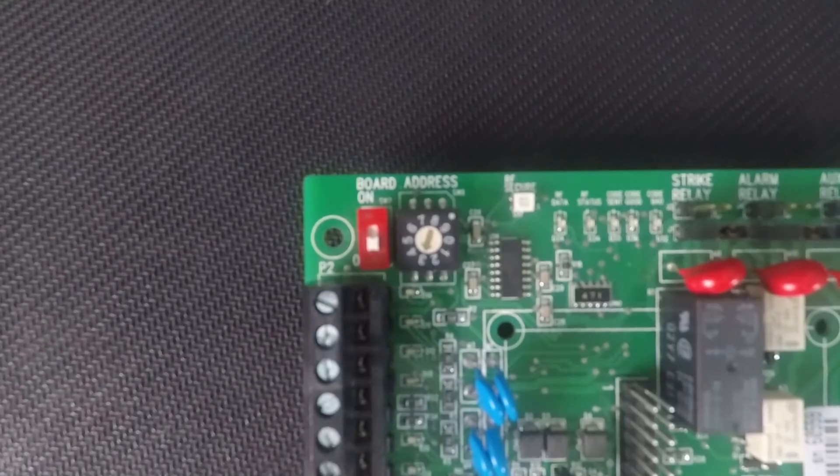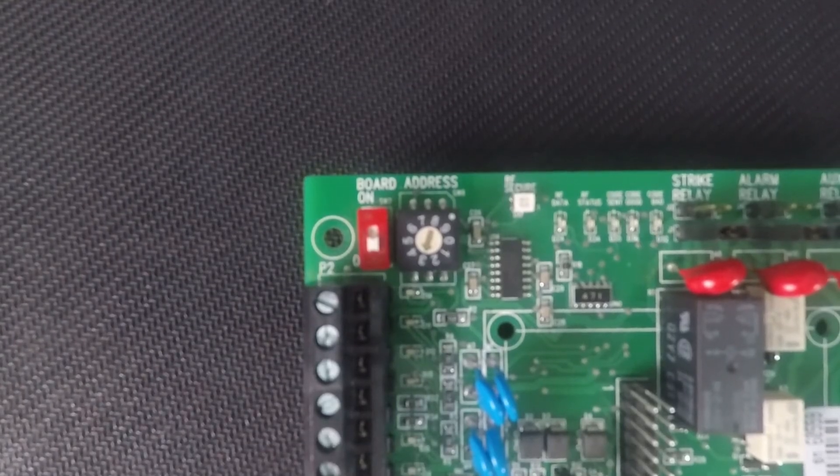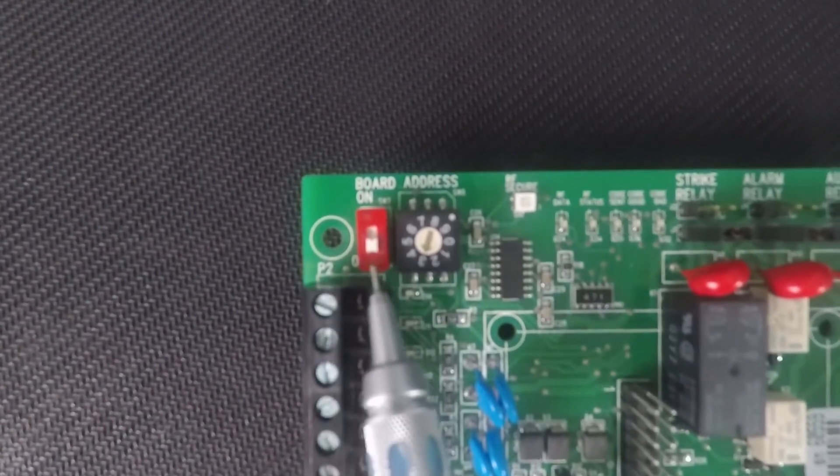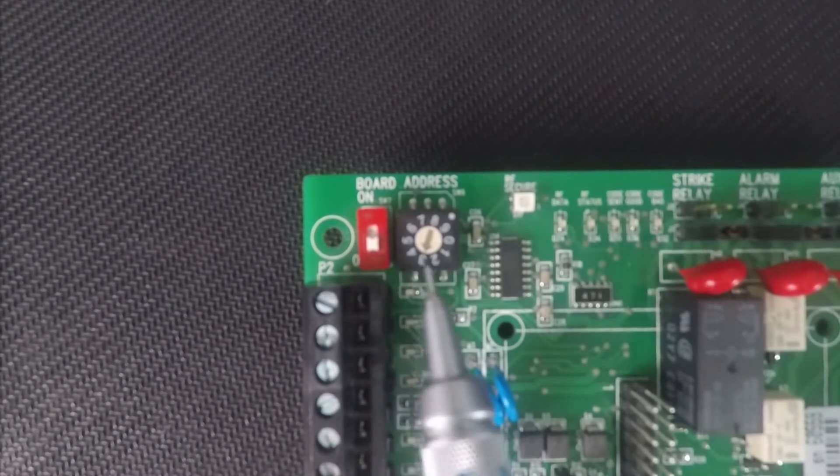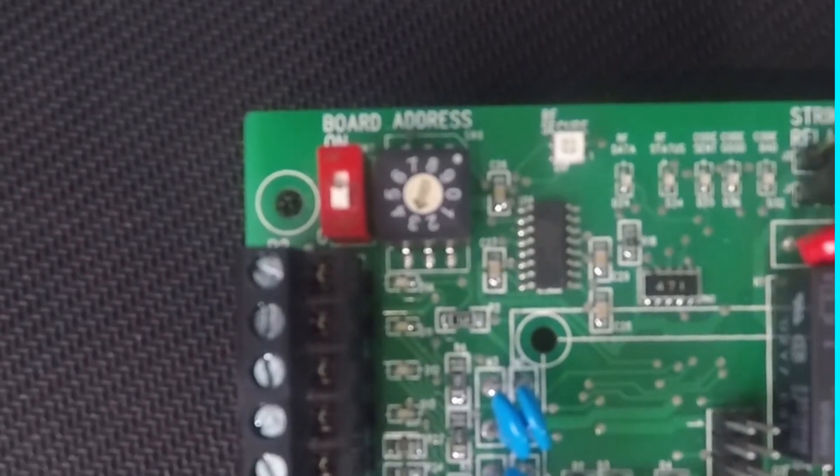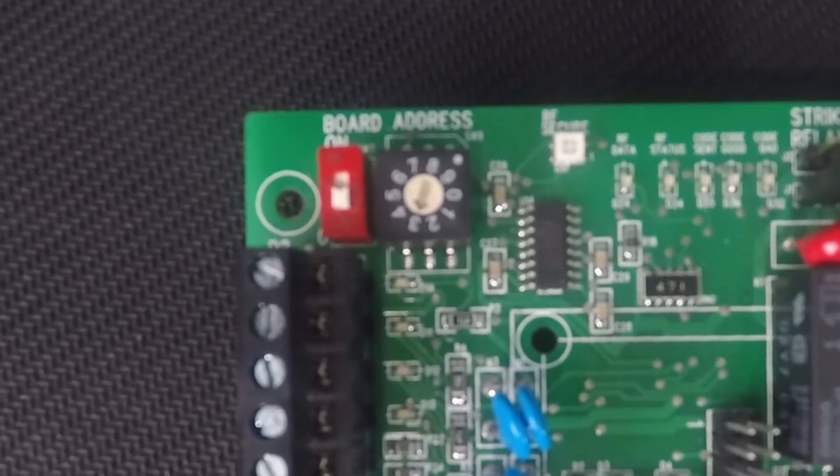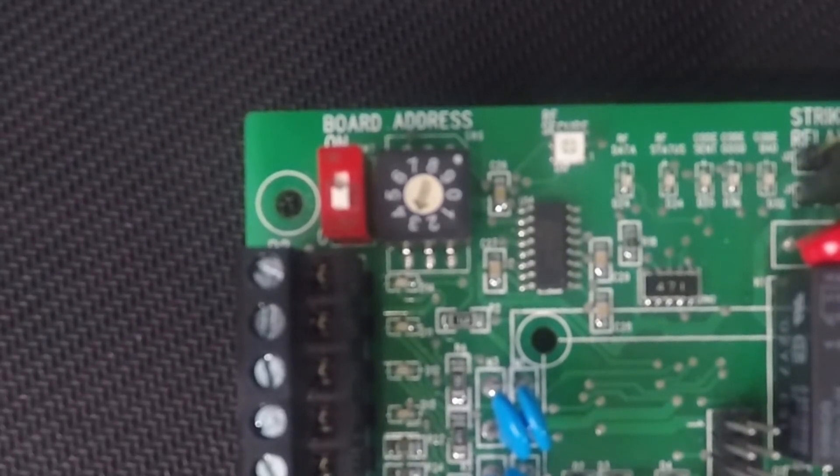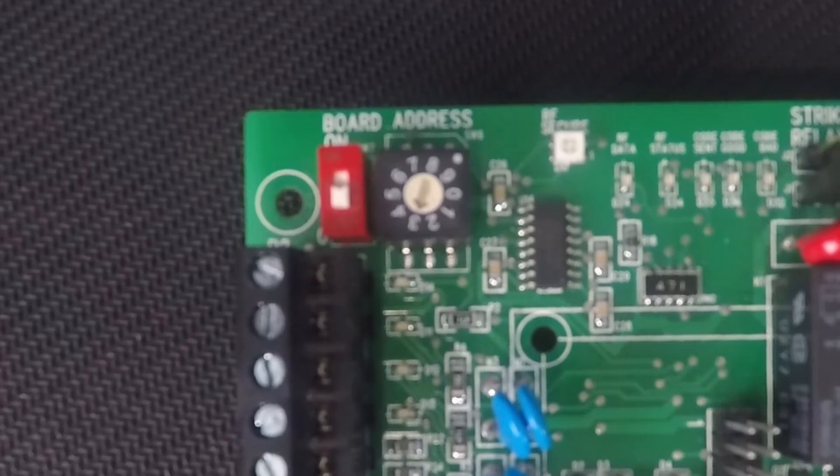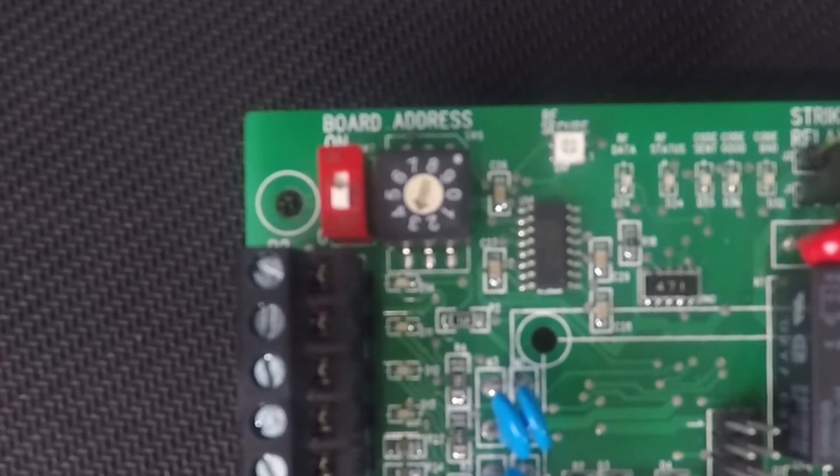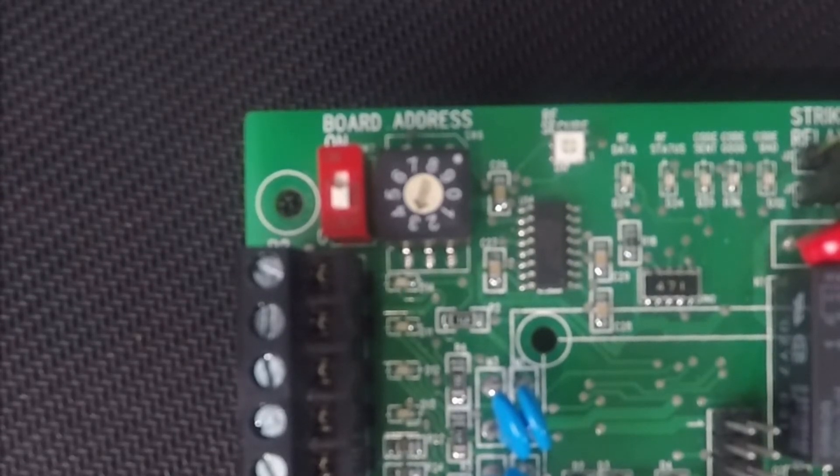The relay number or board address on the tracker board is made from a switch and a dial. Valid tracker board addresses or relay numbers are going to be from 03 to 18, with tracker boards 03 through 10 being attached to Wiegand input 2 and 11 through 18 attached to Wiegand input 1.